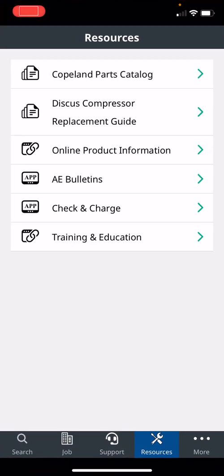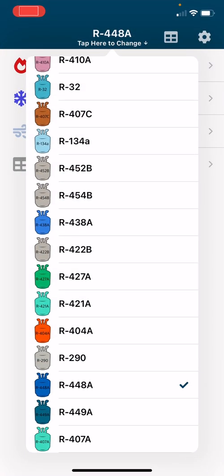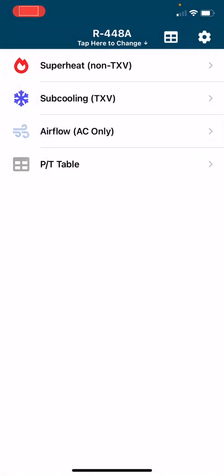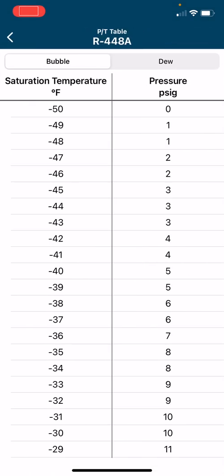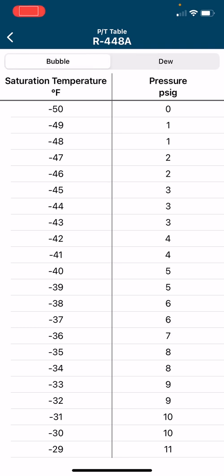Other features that we added: quick resource check and charge. Here in the check and charge, this is going to help you figure out if you had too much charge in the system or not. We are going to say a 448 system right now. If you click up in the top box here, it is going to give right here, it will give you the PT chart table. So this is your bubble point, here is your dew point. There's two different ones here because this is a blended refrigerant, there is glide. You always want to make sure you use dew point for your superheat, you use bubble point for your subcooling, because if you use bubble point to try to do superheat, you can potentially flood that compressor out.